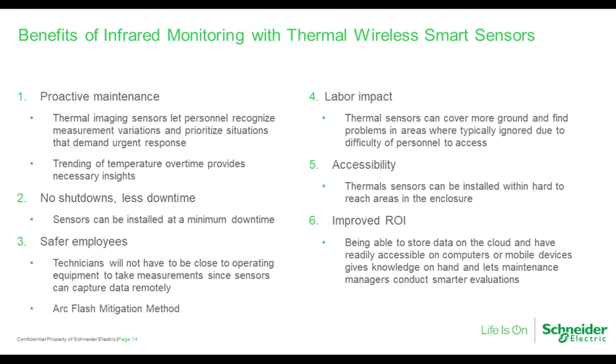And it's also safer for the employees because once these sensors are installed, the technicians no longer have to be close to operating equipment to take measurements. Even with thermographics and even with windows, it does put the employee in front of the equipment. So these are some great arc flash mitigation methods to keep employees safe and away from the equipment.